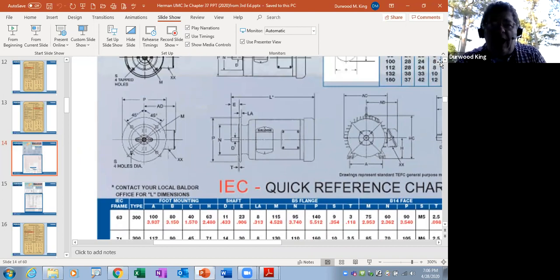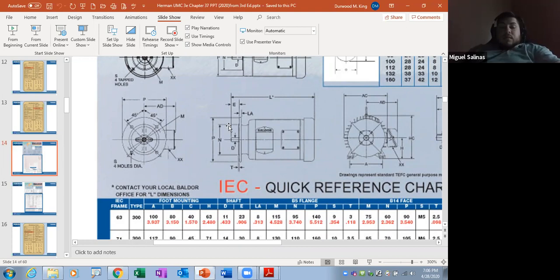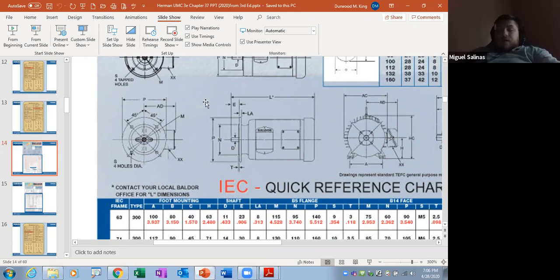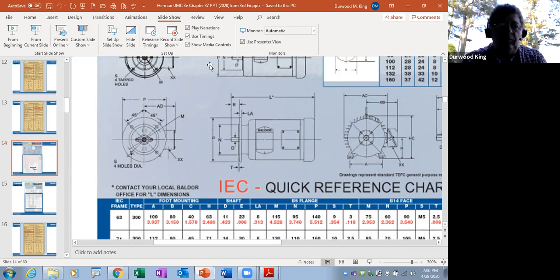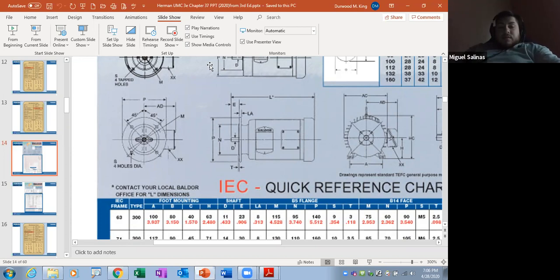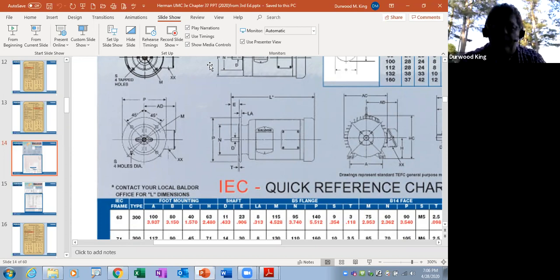McGill and Victor, you got IEC and you got NEMA out there at the plant, don't you? As far as I know, we just got the NEMA. Okay. They might have some on the other side. As far as our area, we just got NEMA. The only things we usually deal with is the 143 TC. Yep. Or the 143 or the 56C or the 56. That's all we really deal with. Those numbers sound familiar from where I was at. They're real common frame sizes and all.